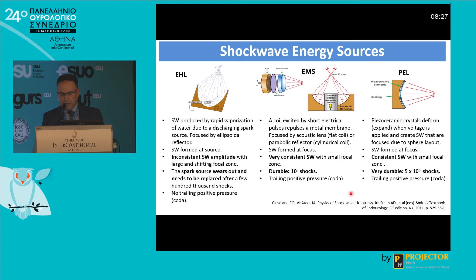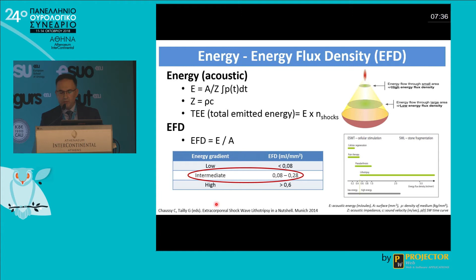Perhaps the most important parameters when talking about shockwave treatment are energy and energy flux density. The energy is inversely proportional to the acoustic impedance of the tissue, which is a measure of tissue density and sound velocity in the medium. That means that we can carry energy through the human tissue because it has the same acoustic impedance as liquids. That's why we have to use coupling, a coupling gel or a water bath. Energy flux density is a measure of the concentration of energy over a given area. And in low-intensity shockwave therapy, we use intermediate settings because, again, we don't want to break stones. We want to promote angiogenesis.